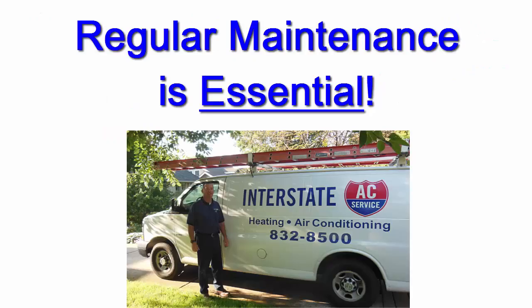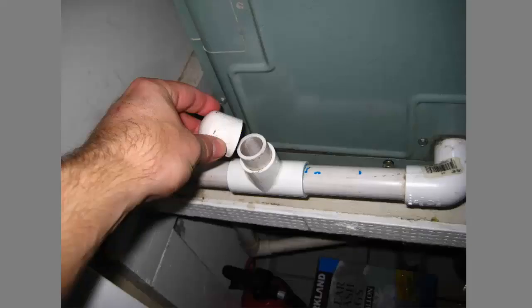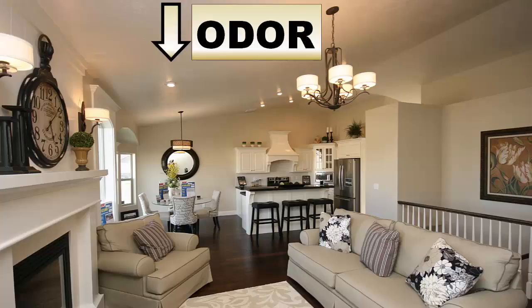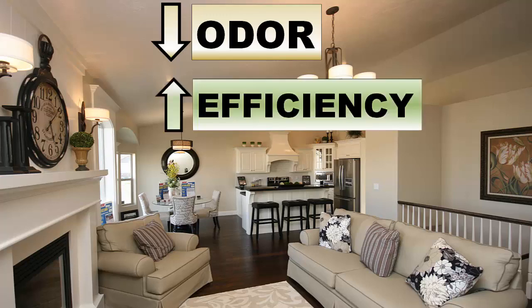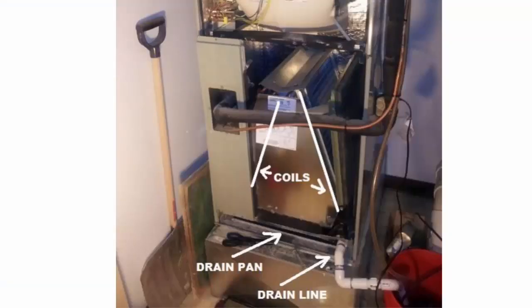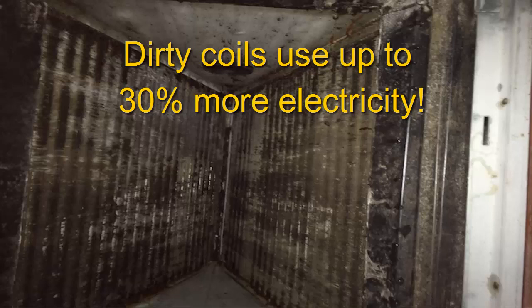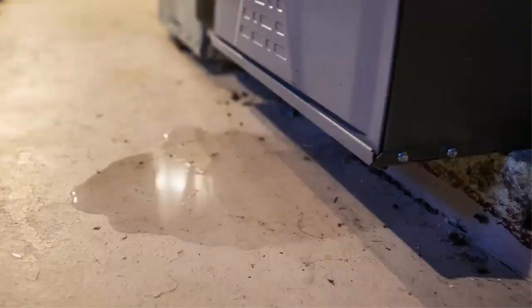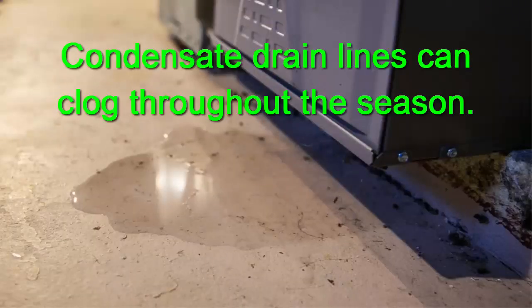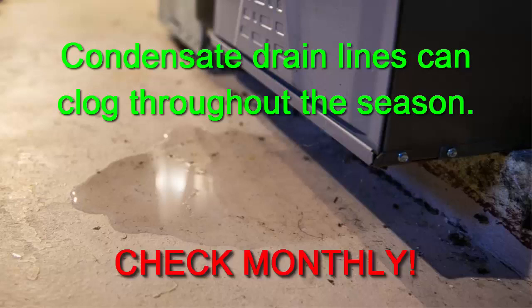To prevent this, regular maintenance is essential. As part of regular spring and summer HVAC maintenance, the evaporator coil and condensation lines are cleaned. Doing this not only works to reduce smell, but the procedure will also improve the efficiency of your air conditioner. The mold, mildew, and dirt deposited on your coil will reduce airflow through the system, lowering its efficiency and causing your HVAC to fail sooner. But even if you've had your system cleaned at the beginning of the season, the condensate drain line could still become clogged during the course of use. So it is important to check the condensate pan and drain lines monthly throughout the air conditioning season.